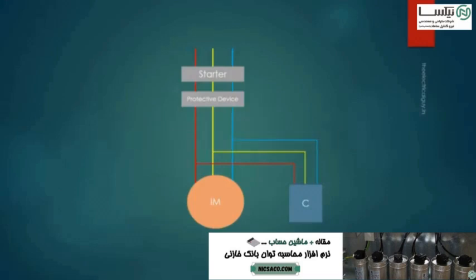So we'll get started with the distributed power factor correction. In this type of power factor correction, capacitor banks are directly connected to the terminal of the load which demands reactive power. This type of installation is very economical and simple. The capacitor bank and the load can use the same protective device against overcurrent as shown in the figure, and can be connected and disconnected simultaneously. This type of power factor correction is advisable for large loads which remain connected to the system for a long time. This type of correction is generally used for induction motors and fluorescent lamps.